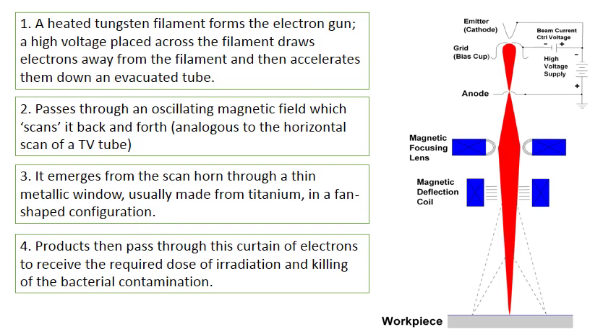In terms of how it works mechanically: a heated tungsten filament forms the electron gun. A high voltage is placed across the filament, which draws electrons away and accelerates them down an evacuated tube. As electrons travel through the tube, they pass through oscillating magnetic fields which scan them back and forth like a TV tube. They emerge in a fan-shaped configuration, and products pass through this fan of electrons on a conveyor belt, receiving the required dose of irradiation to kill bacterial contamination.